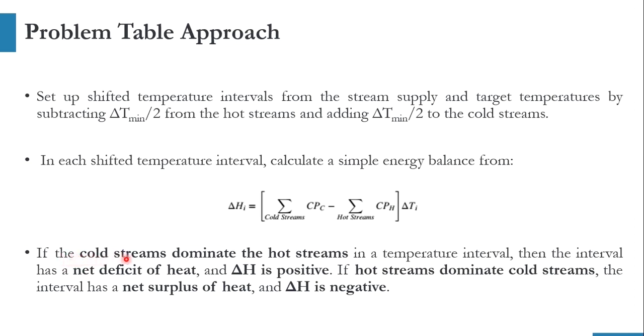One important thing: if the cold stream dominates the hot stream — meaning CP of C is higher than CP of H — then the interval has a net deficit, meaning we need to supply heat, and delta H is positive. If the hot stream dominates the cold stream, the interval has a net surplus of heat and delta H is negative.